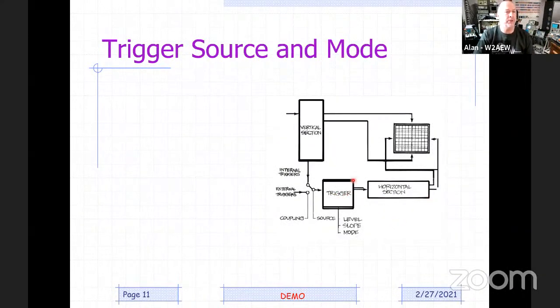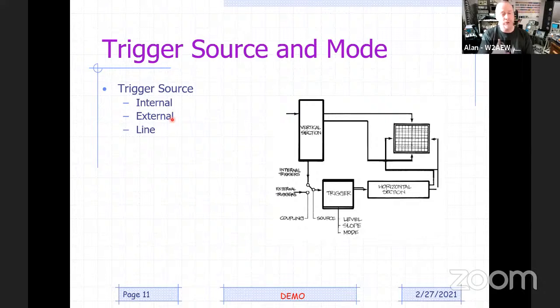So again, triggering is going to pick off signals from the vertical input, because we want to look at the input that we're sending into the scope and lock on a portion of that and then send off the sweep to start at that location on our waveform. You typically can get signals from the input or an external, a separate input to trigger. We can talk about coupling and the sources. That's going to provide an input like the trigger on a gun to kick off the horizontal sweep. The trigger source is typically internal, which means I'm going to pick off a portion of my input signal as my reference of what I want to trigger on. 99% of the time, that's what you're doing. You might have another signal source you want to trigger from.